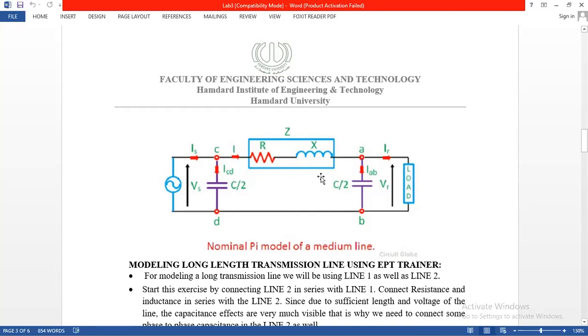So further parameters we need to see at this side are A, B, C, and D, which are the terminal ends. A and B are the receiving end terminals, and C and D are the sending end terminals of the power transmission line. The combination of resistance and reactance becomes impedance, mostly used in AC circuits. The current flowing in the capacitance of the parallel branch at the terminal between C and D is called ICD, and the current flowing from A to B ends is called IAB. So these are the modeling of the pi model of medium transmission line.